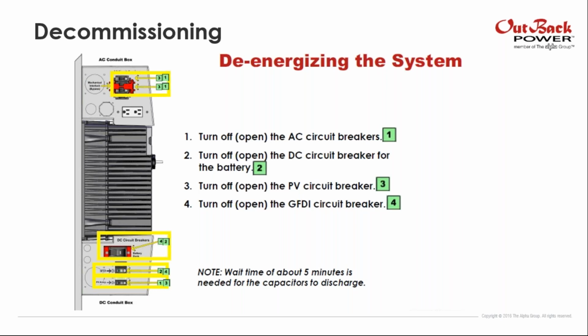So the way to do the decommissioning is exactly the opposite of what we have done for commissioning. First of all, you need to turn off the AC circuit breakers, I mean, in order to open them so that you do not have power to the loads or the AC input. Then you have to turn off the DC circuit breaker for the battery, I mean the big one. Then turn off the PV circuit breaker. It's here. And turn off the GFDI circuit breaker.